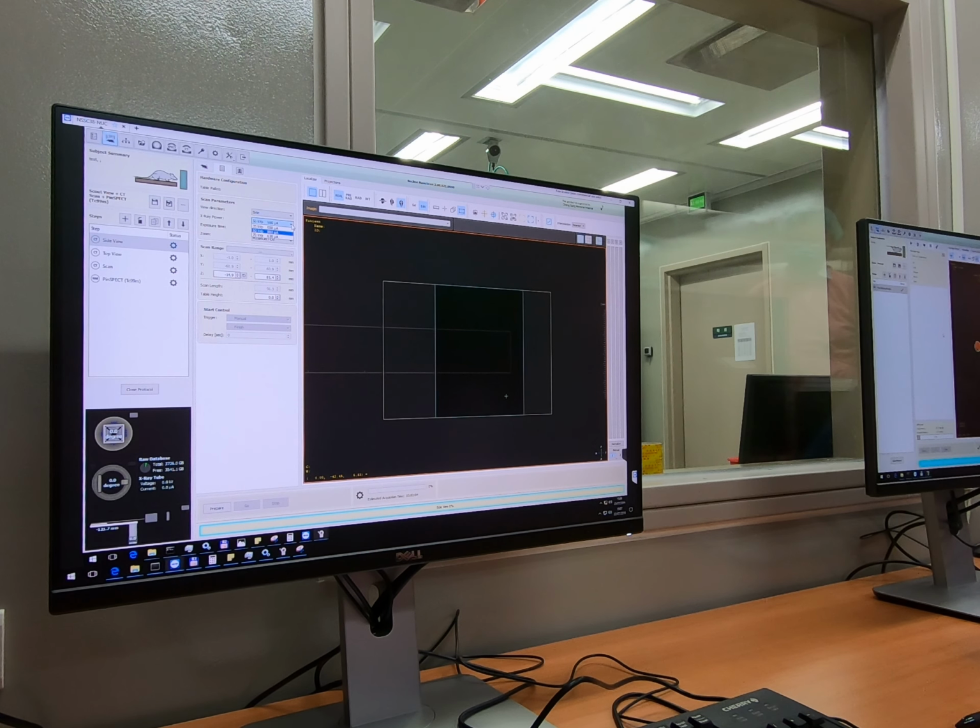Contrast. So what do you mean? It actually modifies the energy of it. Yeah, so if you have to image something big, bigger in the field of view, like a fat rat, we use the higher power. Yeah, higher power, because if the animal has really dense and thick bones, for example, you will need photons with higher energies, because otherwise most of their energies will be absorbed in the tissue and will not really reach the detector. Okay, and what is the indication for lower power?